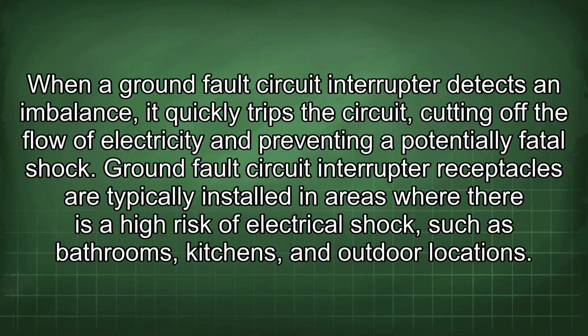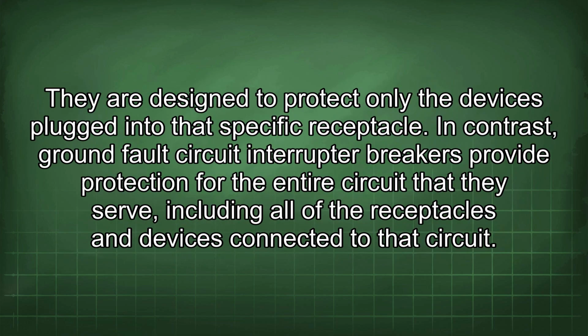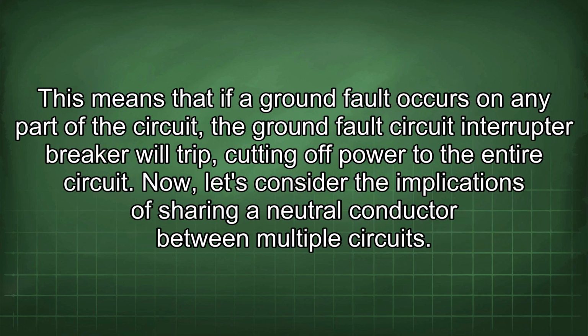Ground fault circuit interrupter receptacles are typically installed in areas where there is a high risk of electrical shock, such as bathrooms, kitchens, and outdoor locations. They are designed to protect only the devices plugged into the specific receptacle. In contrast, ground fault circuit interrupter breakers provide protection for the entire circuit that they serve, including all of the receptacles and devices connected to that circuit. This means that if a ground fault occurs on any part of the circuit, the ground fault circuit interrupter breaker will trip, cutting off power to the entire circuit.